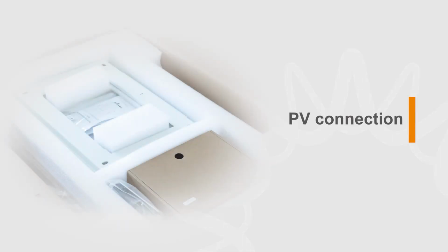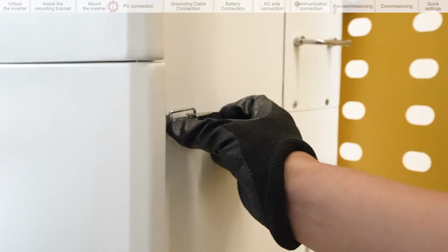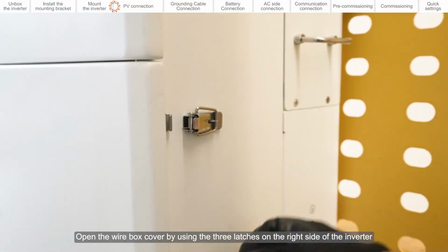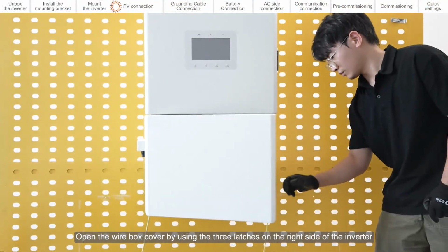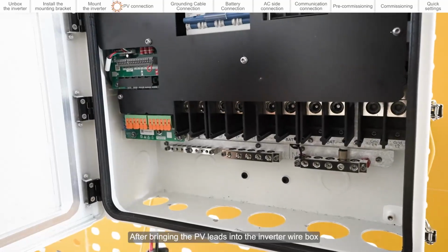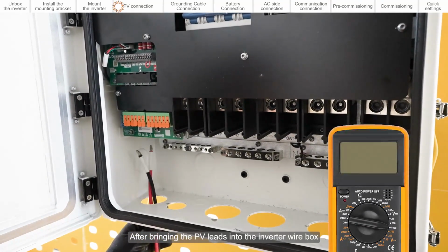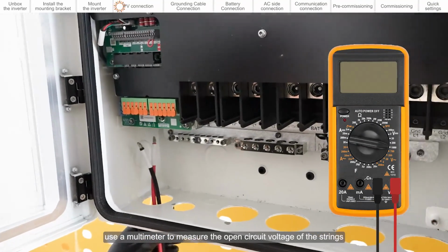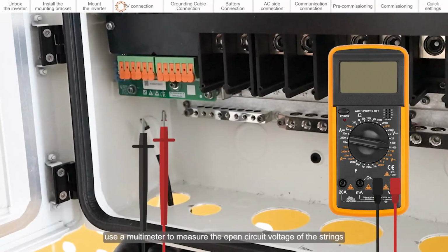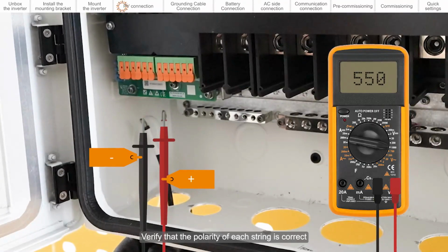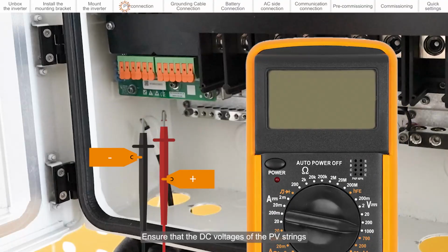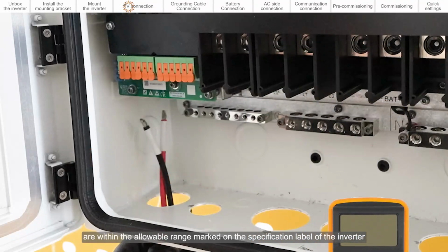PV connection. Open the wire box cover by using the 3 latches on the right side of the inverter. After bringing the PV leads into the inverter wire box, use a multimeter to measure the open circuit voltage of the strings. Verify that the polarity of each string is correct. Ensure that the DC voltages of the PV strings are within the allowable range marked on the specification label of the inverter.